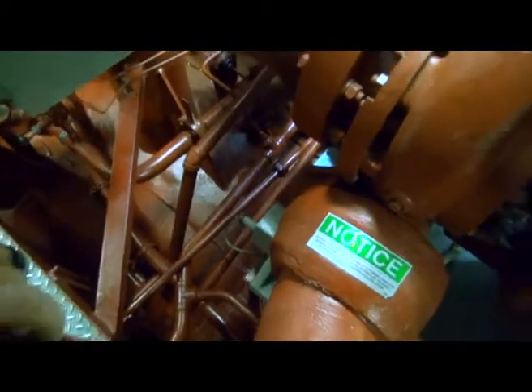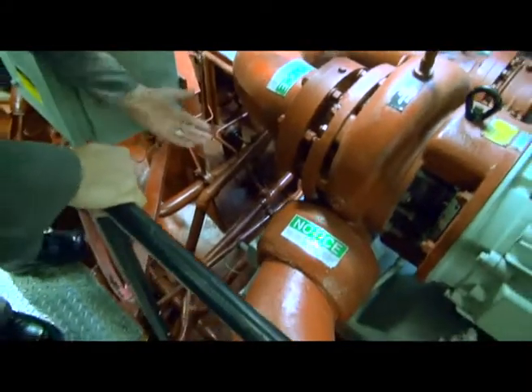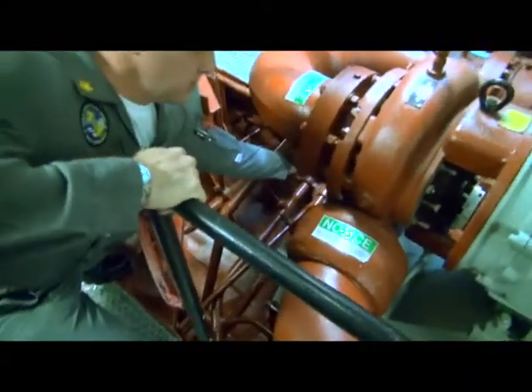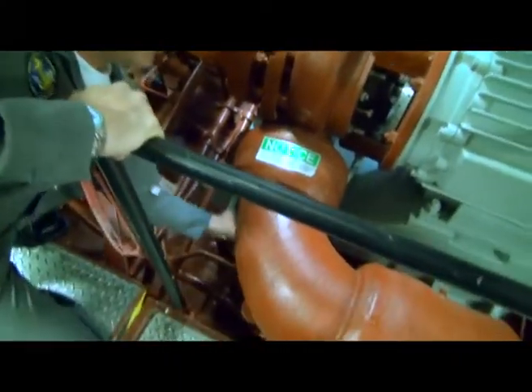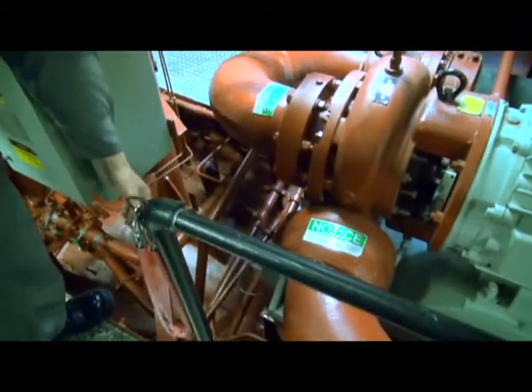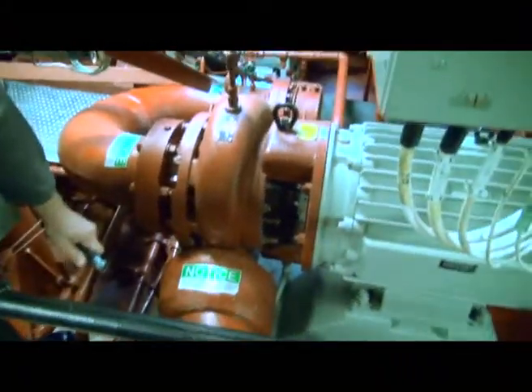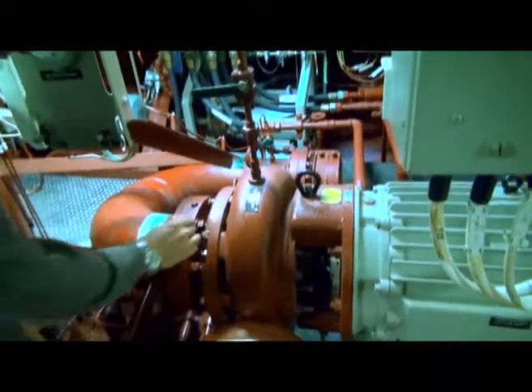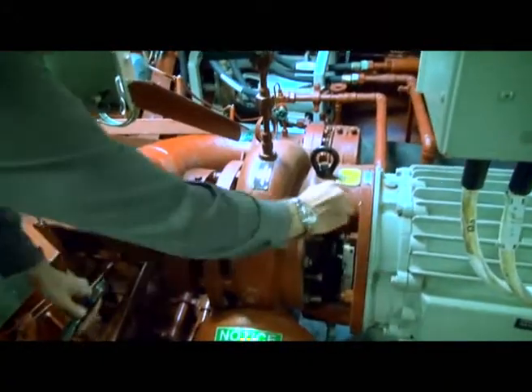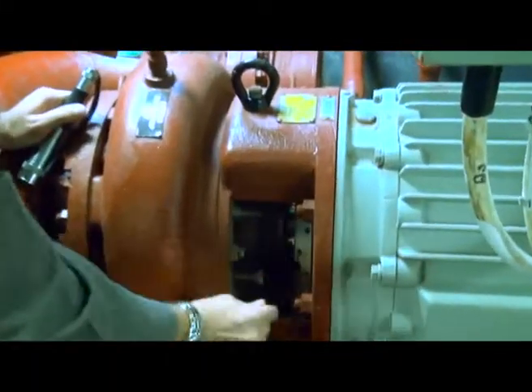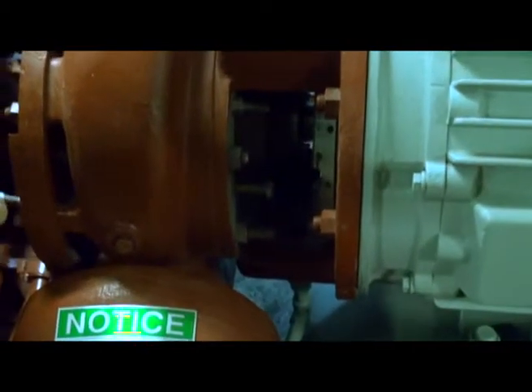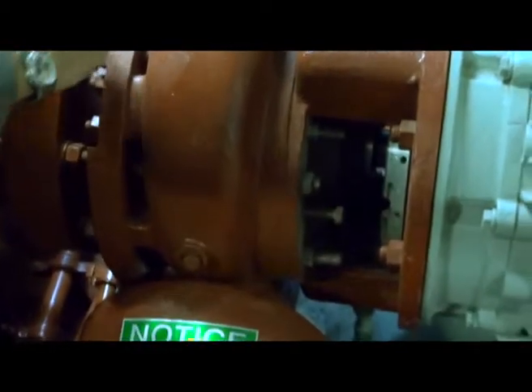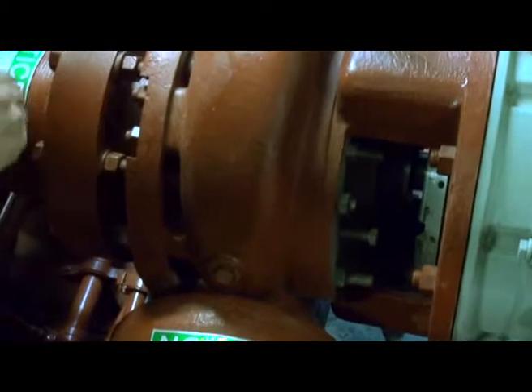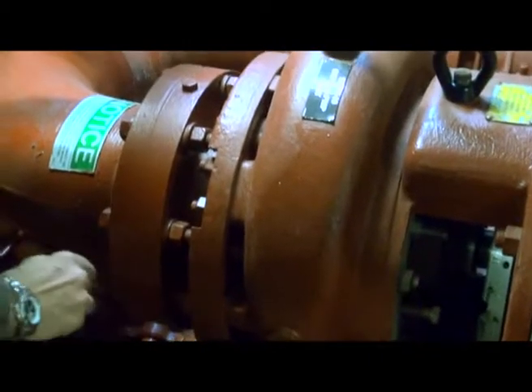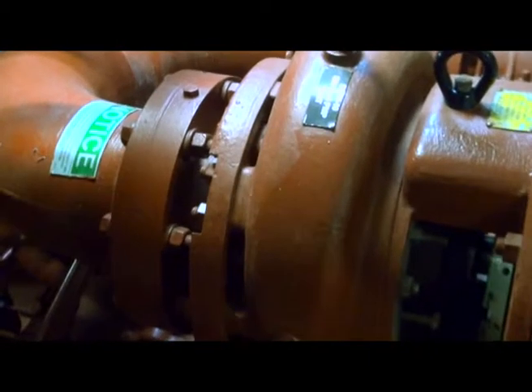So once we start the pump, we do all these checks, and we'll check for leaks too. We'll get under these flanges, check for leaks. Get under this lagging, check for leaks. The other thing I like to do, just like on the fire pumps, is get my magnet out and check for ferrous fasteners. We find those a lot, especially on the older ships. In this case, these are all non-ferrous fasteners. In a non-ferrous system, that's the way we want them.